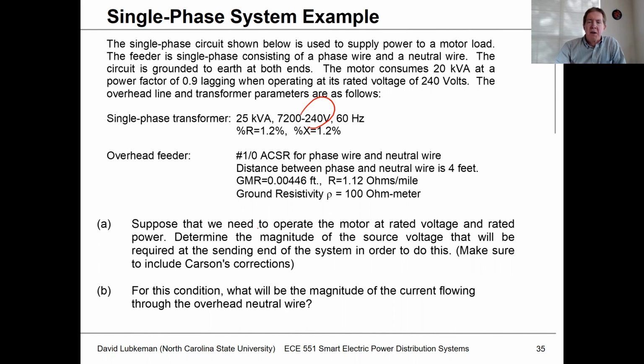And so for the parameter values, I've got a motor that's consuming 20 kVA at a power factor of 0.9 lagging. It's operating at a rated voltage of 240 volts. I'm going to work backwards and figure out the required primary side voltage at the source. So the transformer is 25 kVA. It's got percent resistance and reactance of 1.2%. And then for the overhead, I'm going to have a 1/0 ACSR conductor for both the phase and the neutral wire. The distance between the two is 4 feet.